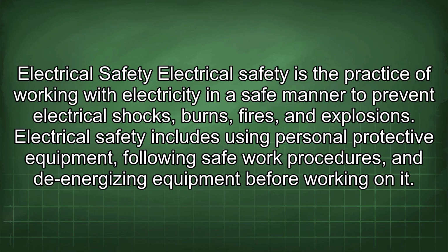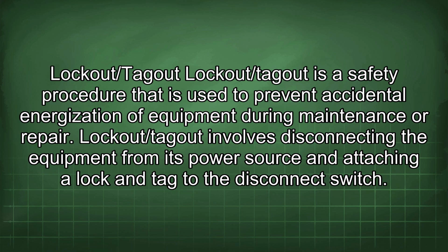Electrical safety. Electrical safety is the practice of working with electricity in a safe manner to prevent electrical shocks, burns, fires, and explosions. Electrical safety includes using personal protective equipment, following safe work procedures, and de-energizing equipment before working on it. Lockout/tagout. Lockout/tagout is a safety procedure that is used to prevent accidental energization of equipment during maintenance or repair. Lockout/tagout involves disconnecting the equipment from its power source and attaching a lock and tag to the disconnect switch.